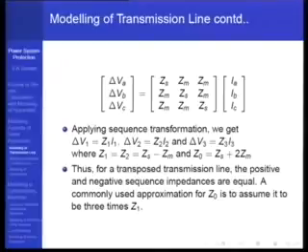And therefore, the estimate of Z0 from design calculations may be far different, maybe 5 to 10% different, from the actual values on the field, because you have made some assumptions on the return and used them here. But positive sequence and negative sequence impedance calculations can be very accurate, up to 2 to 3%.